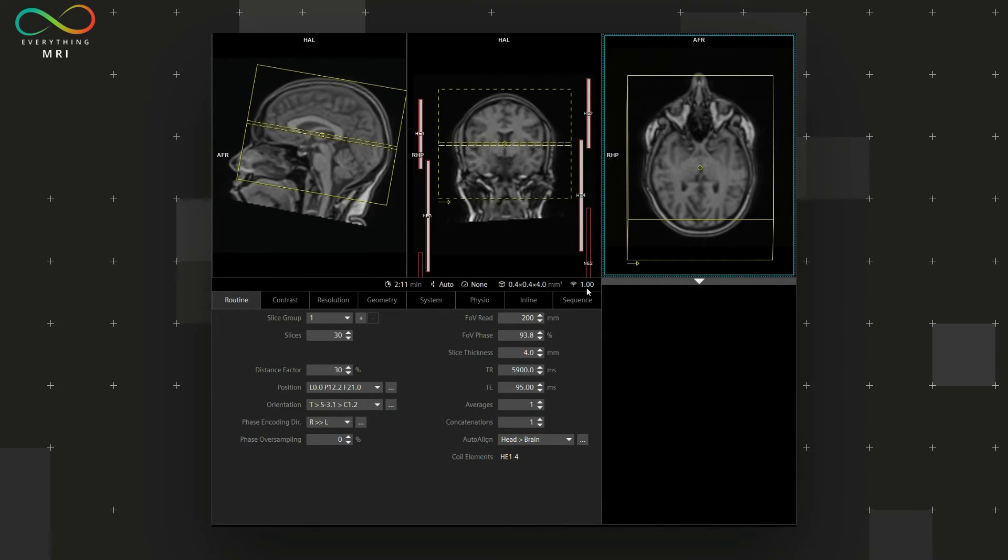However, some MR users prefer to include a minimal amount of oversampling to keep boosting the SNR level, but as we observed previously, this will also increase the scan time. So is this additional step truly necessary? I would say let's find it out together.